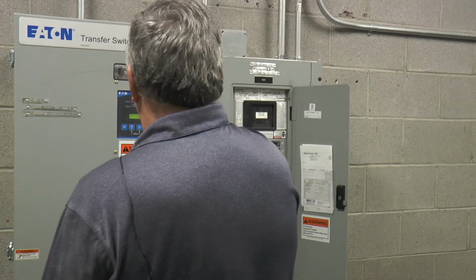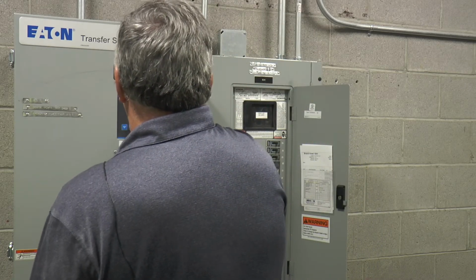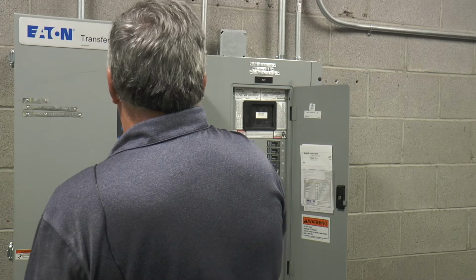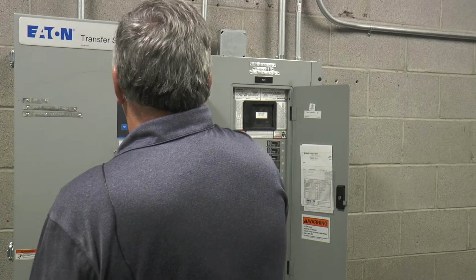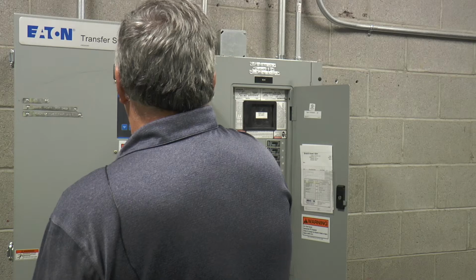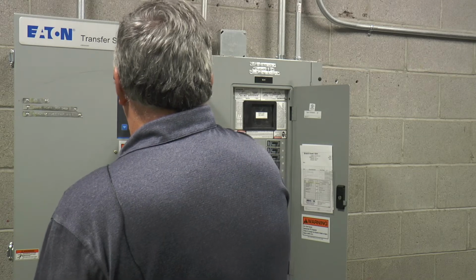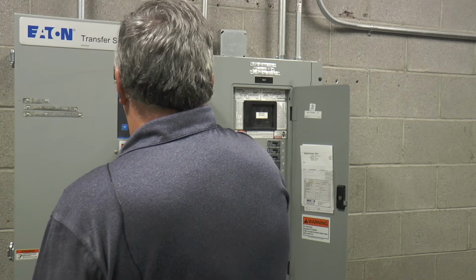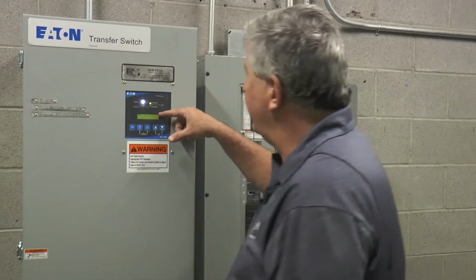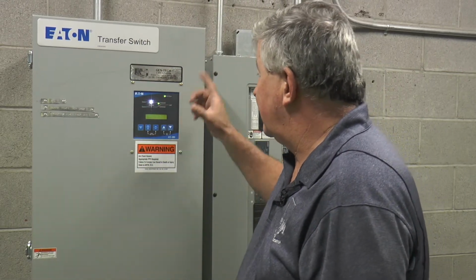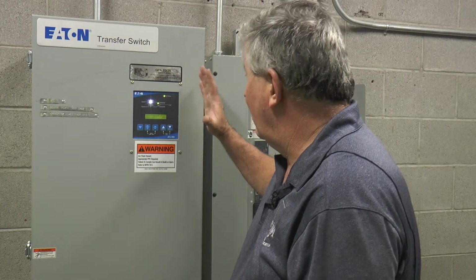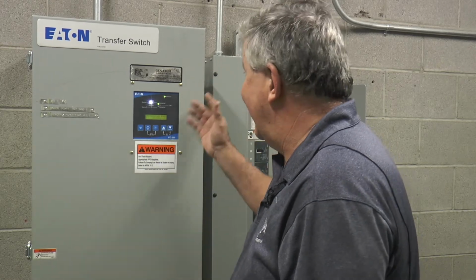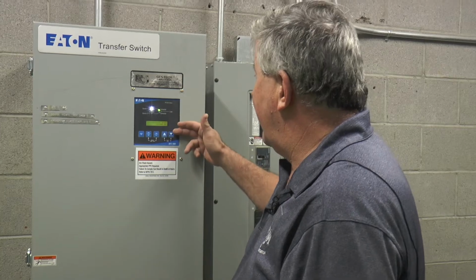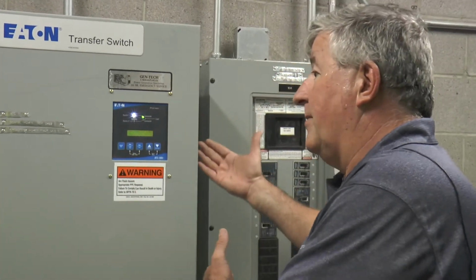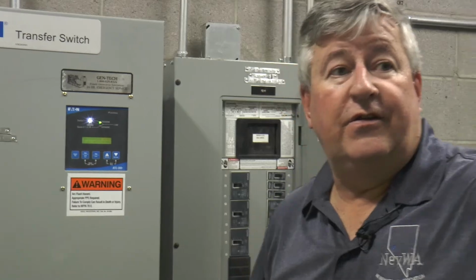Oh, get out of there. Why is that going through? Why aren't you clearing? Going through the relay. It'll clear out. As you go through, it'll give a timer to go out, and for some reason it's giving a little weird communication. But it will go through and time that out and allow this switch to go back to utility. You can do the same for the switch over here on this side too.